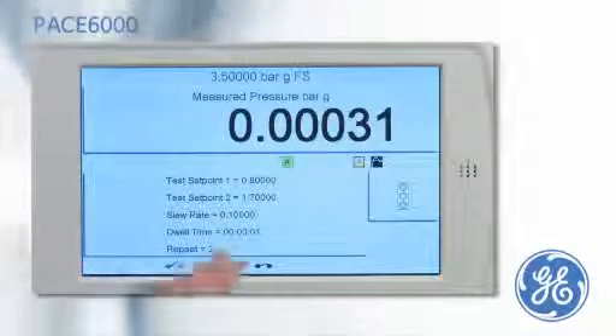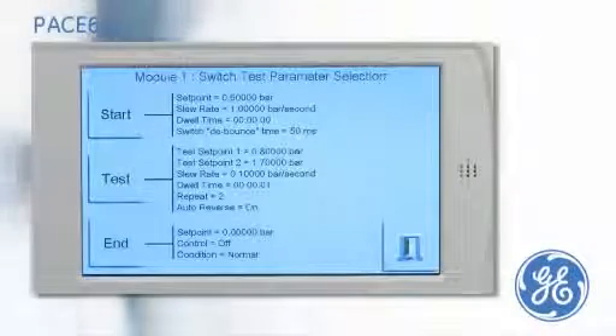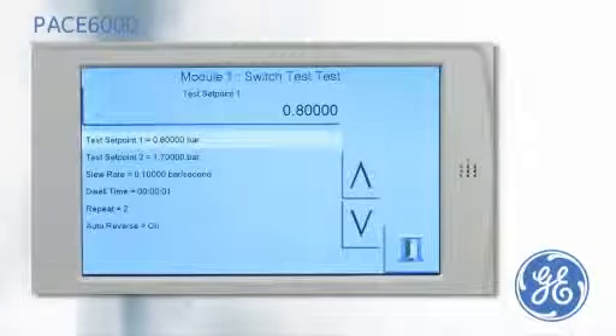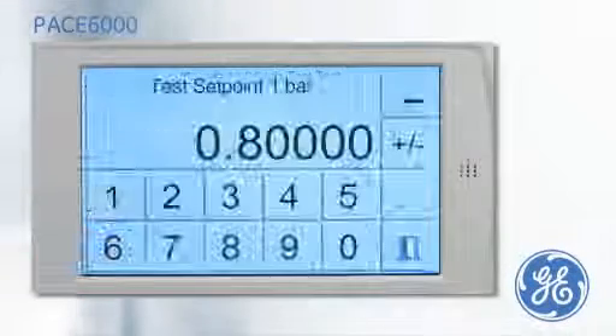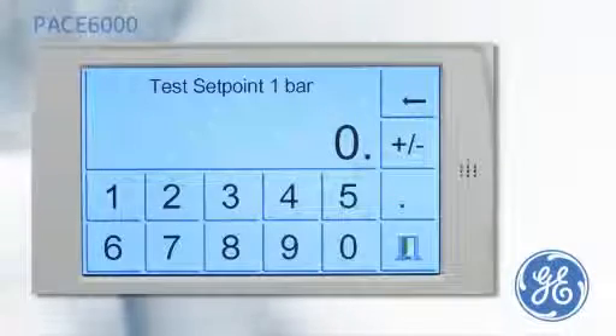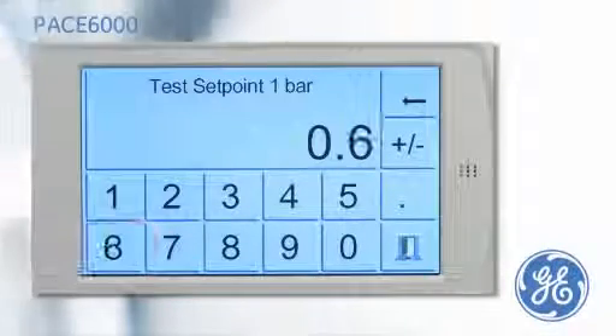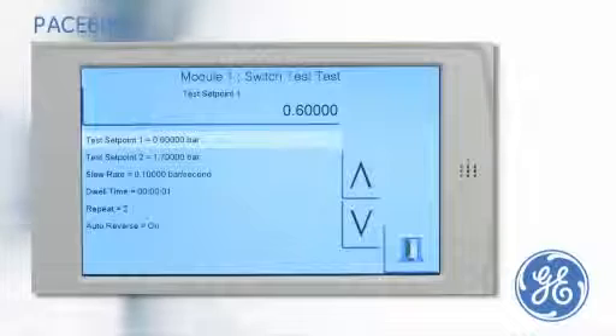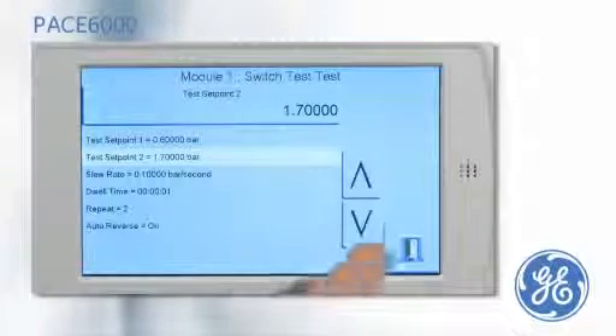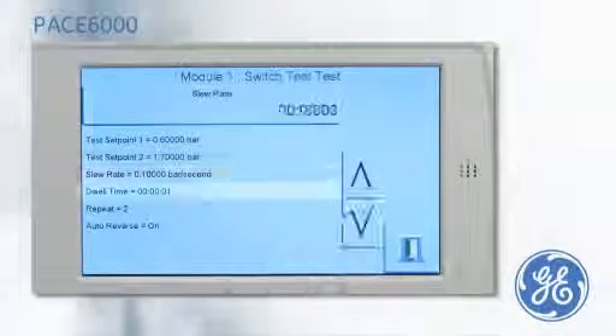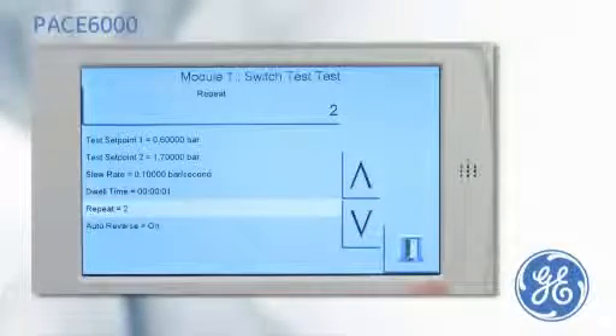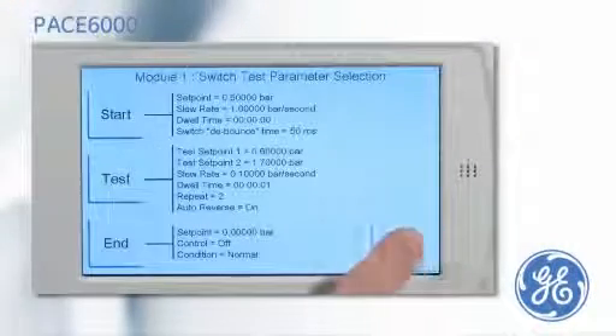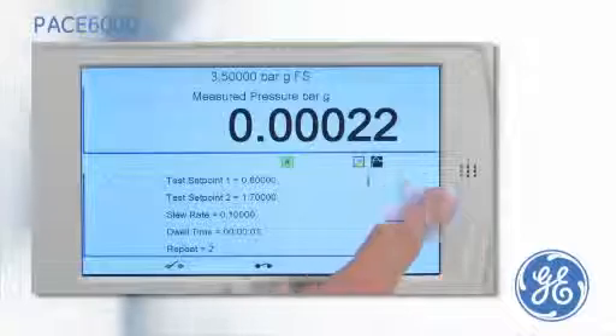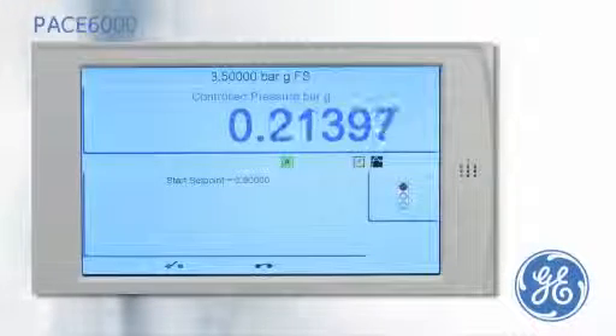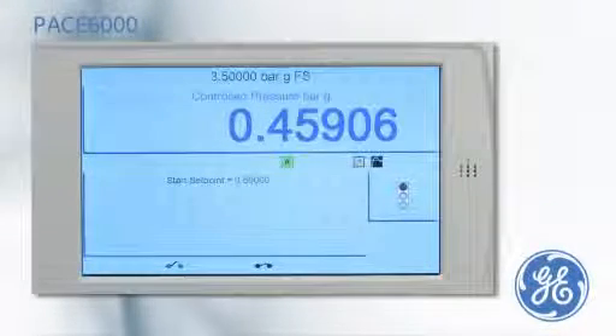From the menu, all start, test and end parameters can be entered. In the test setup, 0.6 is applied as set point 1, which is below the actuation point of the pressure switch under test. Set point 2 is 1.7 bar, which is a higher pressure than the actuation point. Once the test is started, the PACE will achieve the 0.6 start point.